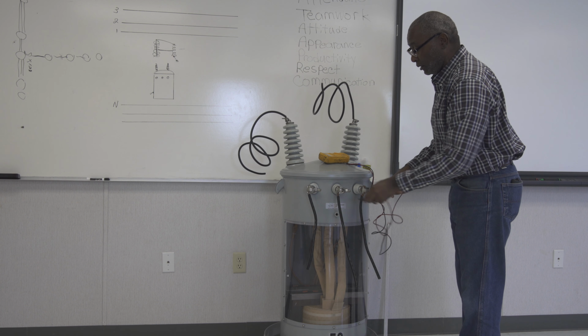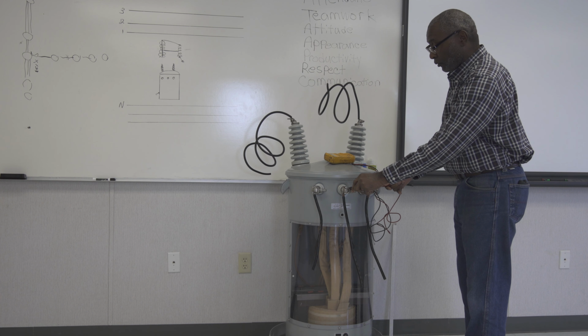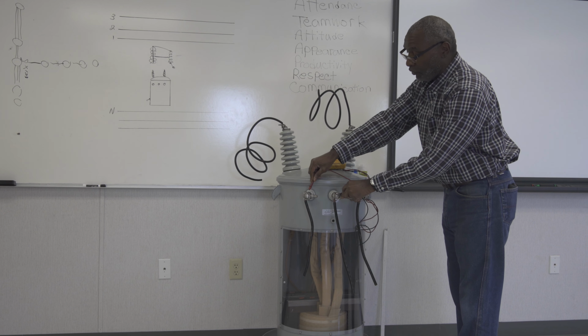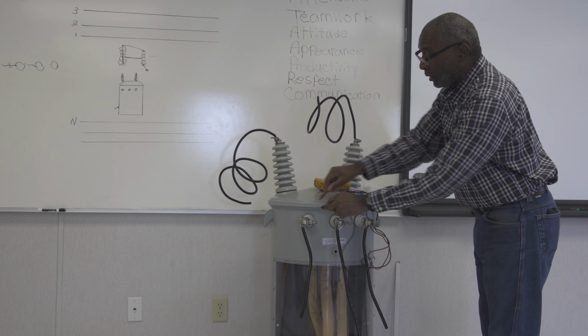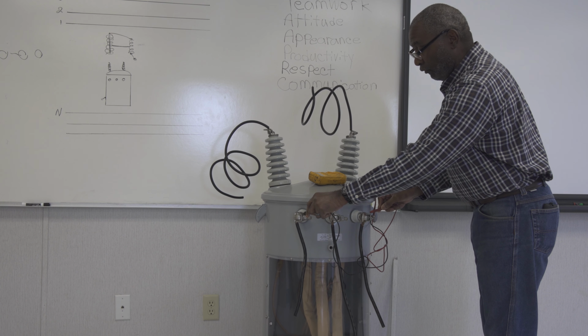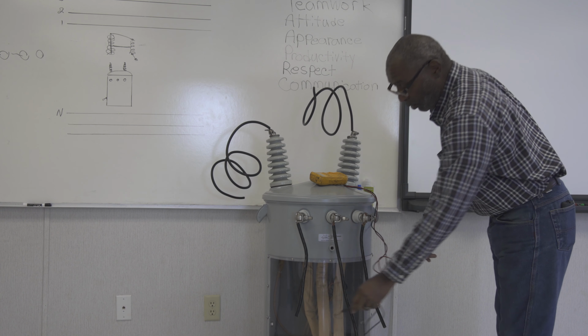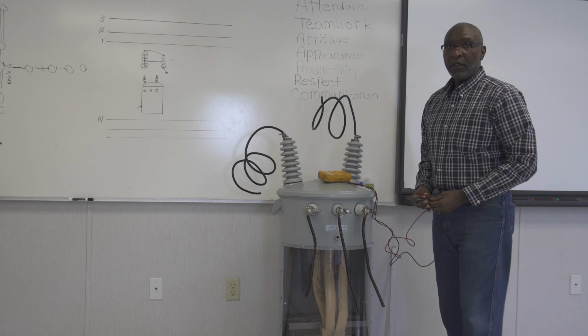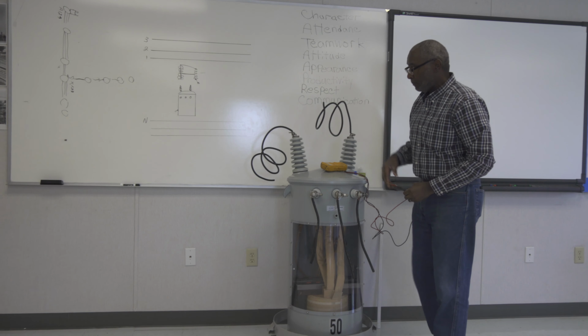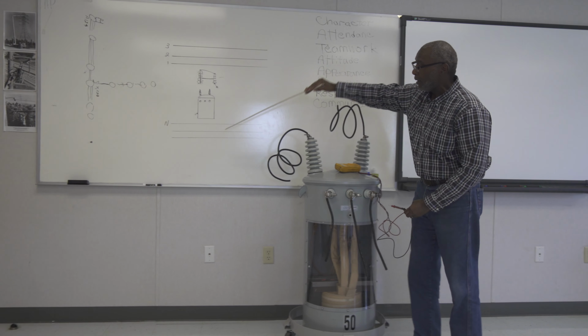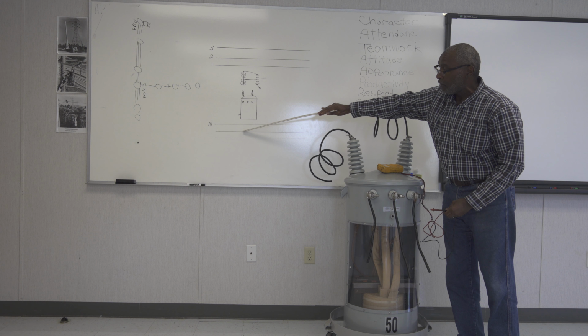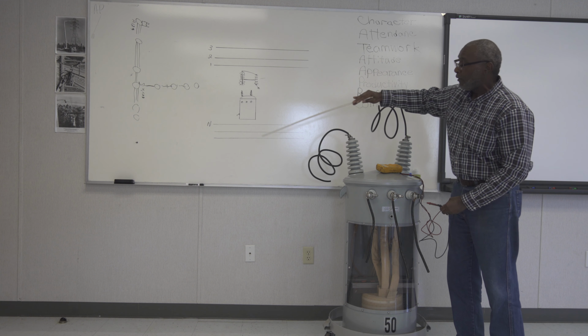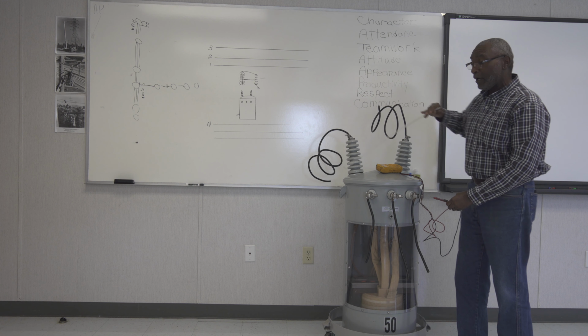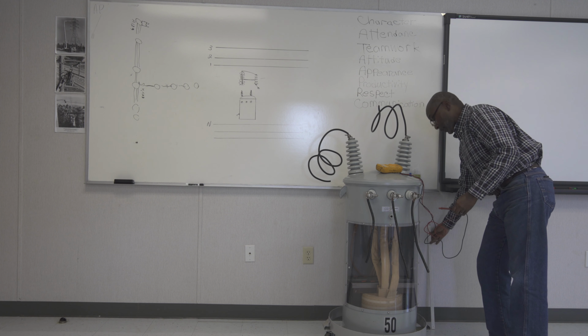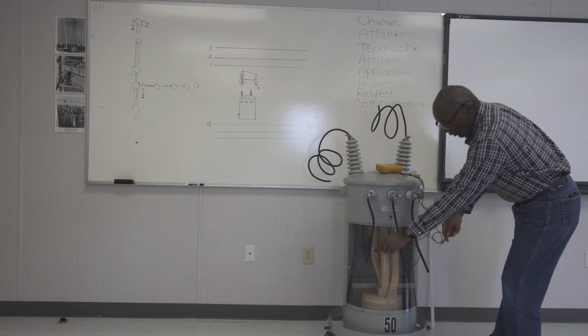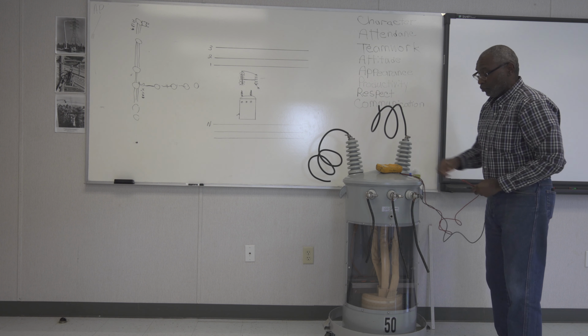Let's do this so you can see. So you got 120 reading on your voltmeter, 120 reading on voltmeter, and across here is going to be 240. Now you can read it here, or right here is where your secondary wire will be hooked up, which is indicating these lines here. That's 120 and that's 120. And in a minute I'll come over and draw all of this out for you as I'm discussing it here. So you can do your measurements down here as well.